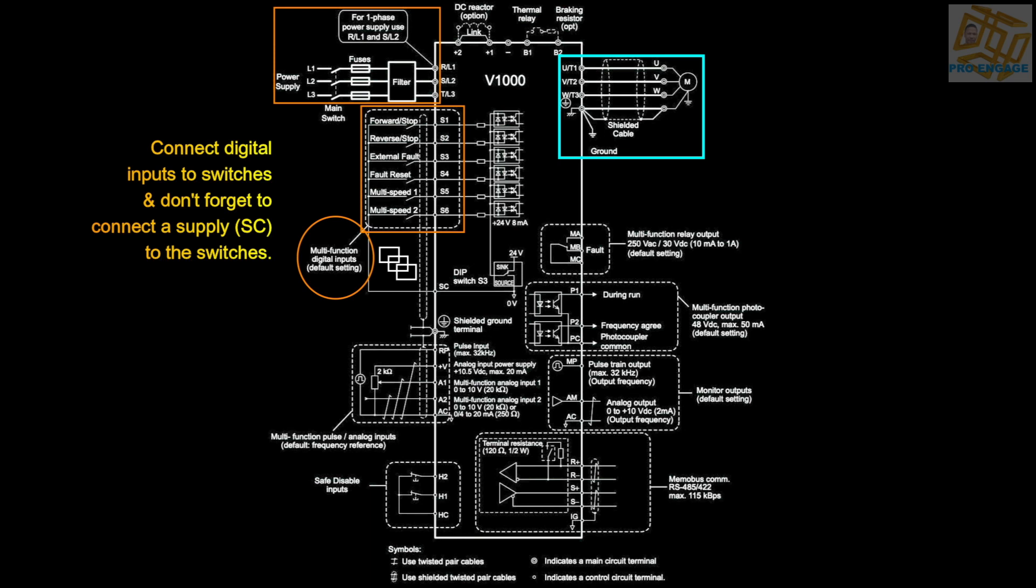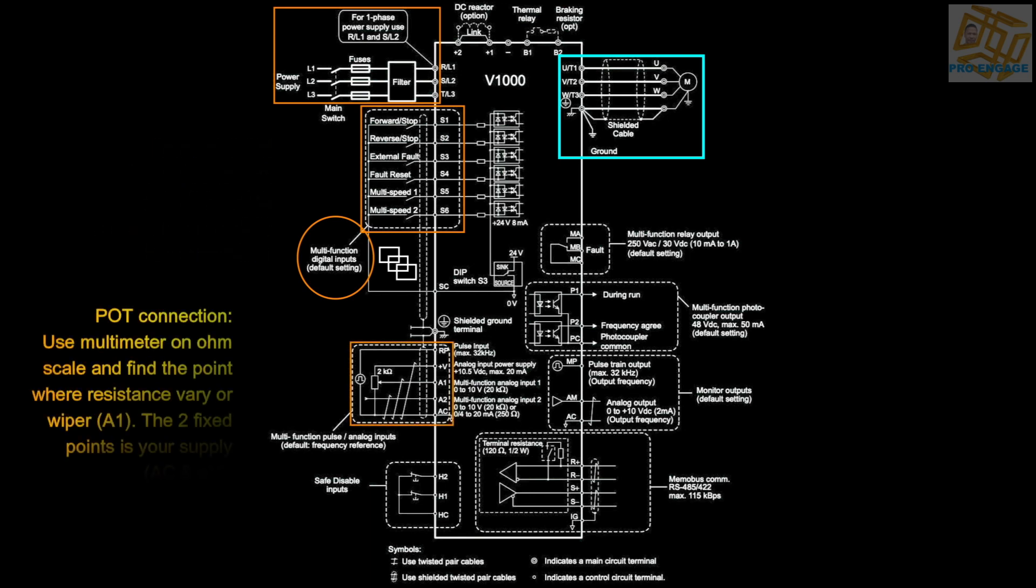We also have to connect the digital inputs to the actual switches. Like any other switch you need to have a supply for it, and that will be SC. There's a potentiometer to vary the speed of the motor, and we can do this by using a multimeter. A1 is very important, which is the wiper on the pot, and the two fixed points are for your supply.